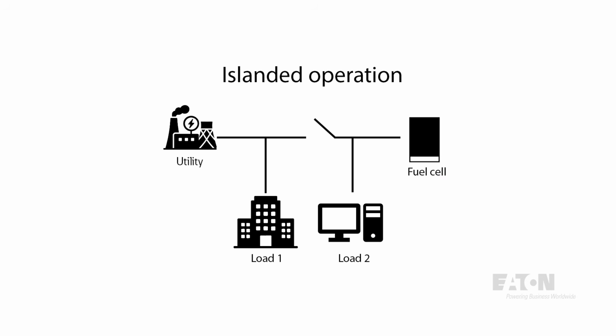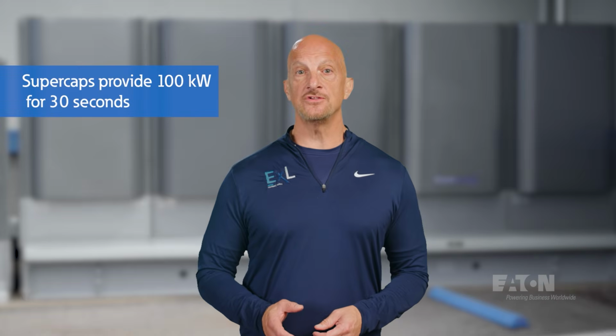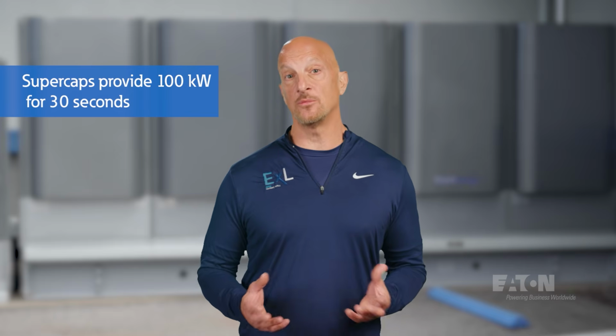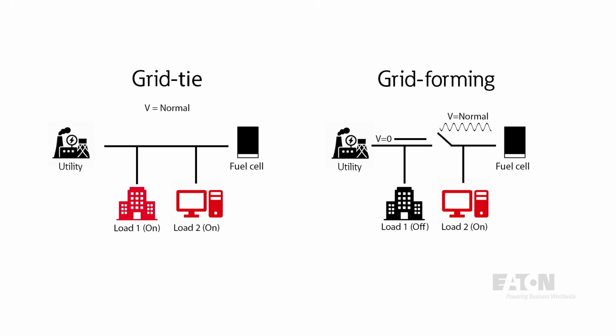In the event of a utility outage, the supercapacitors are used to quickly respond to significant load changes and support islanding of the fuel cell. The supercaps in this unit can support about 100 kilowatts for about 30 seconds. Like a solar-powered inverter, the unit we have is grid-tied, meaning that it will follow and run in parallel with the utility system. But if the utility goes out, it can switch into grid-forming mode where it can island, feeding downstream loads. The supercapacitors help smooth that transition to and from the utility.